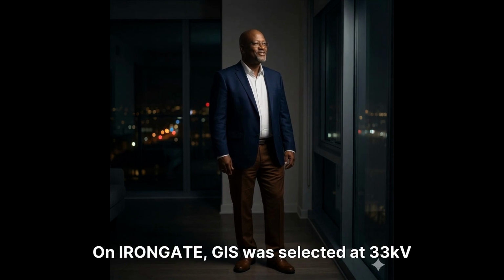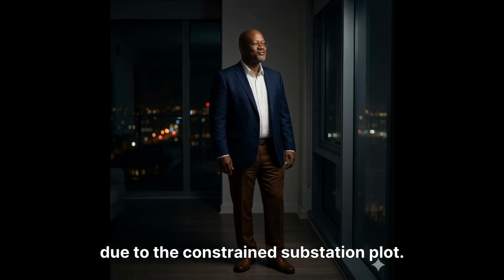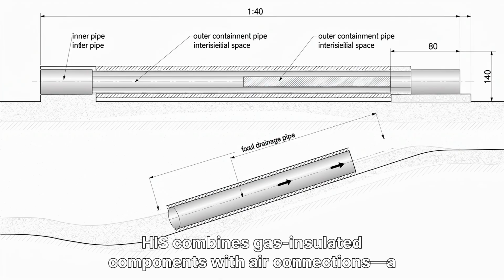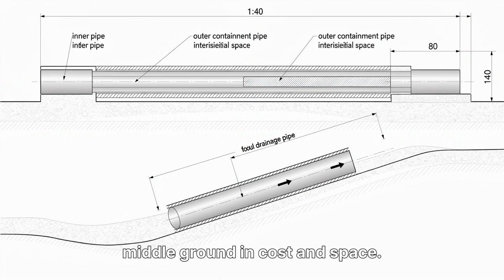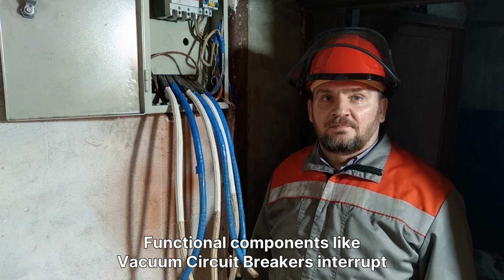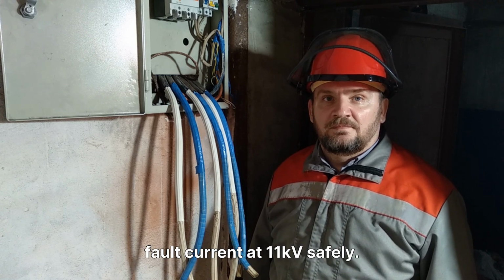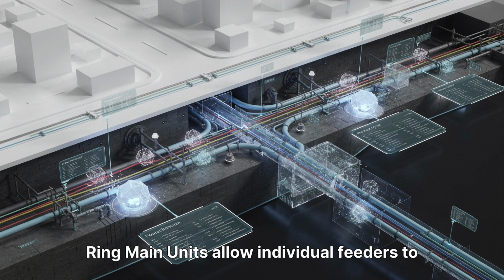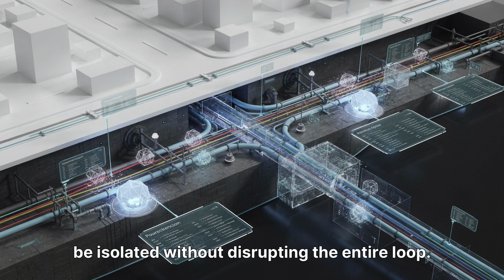On IRONGATE, GIS was selected at 33 kV due to the constrained substation plot. HIS combines gas-insulated components with air connections, a middle ground in cost and space. Functional components like vacuum circuit breakers interrupt fault current at 11 kV safely. Ring main units allow individual feeders to be isolated without disrupting the entire loop.